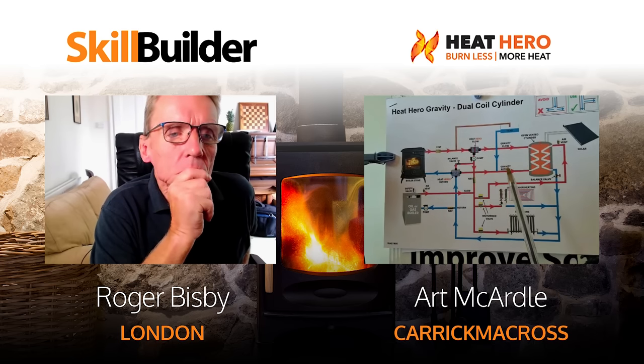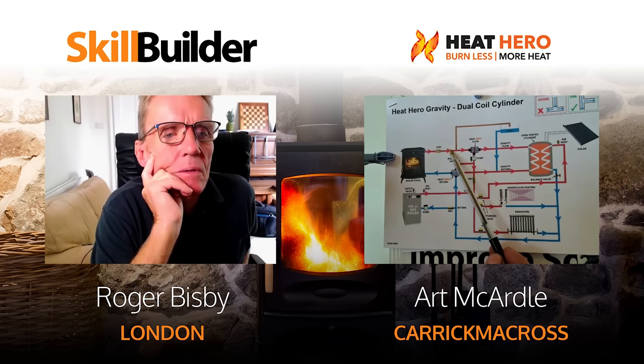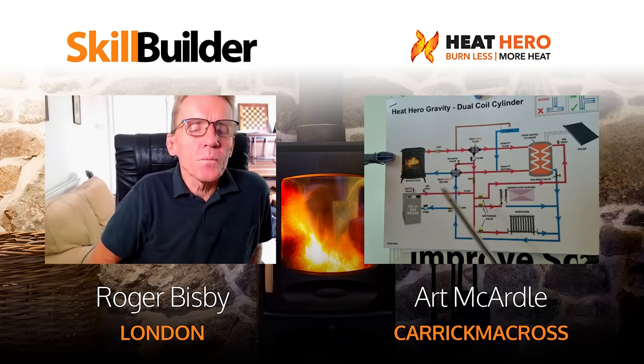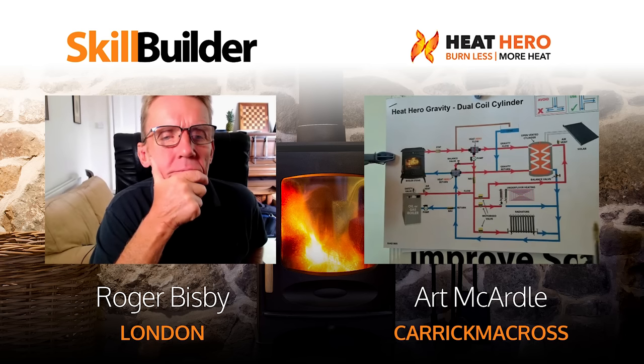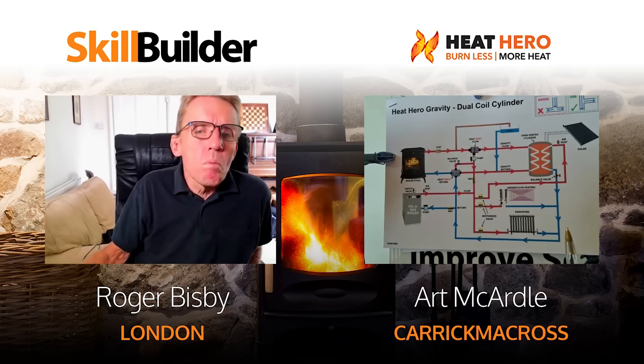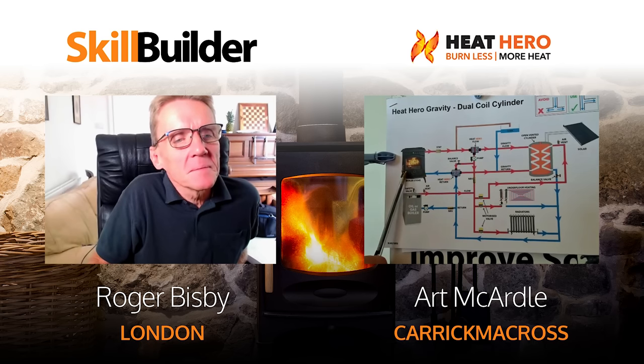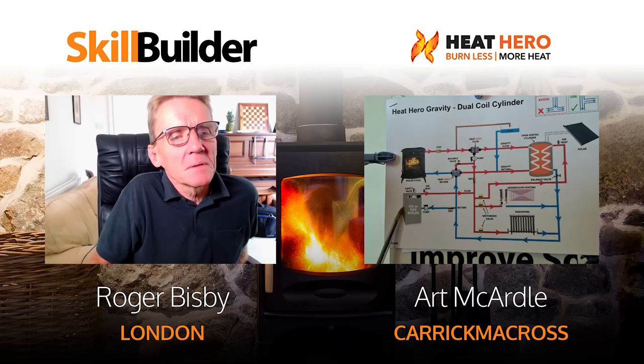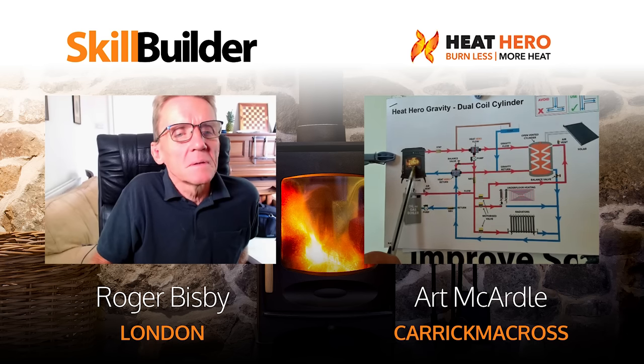We put a second stat on the stove set at about 65 degrees - 10 degrees higher than your standard stat. If it goes above 65 it automatically opens one of the zones to get rid of excess heat. We can do anything we want with solid fuel now. We have a cooker burning wood and have never bought coal - we're heating 23 radiators with it. Waterford Stanley, an Irish stove company with an R&D department, put this through their R&D and now recommend it on their website. You have twice the heat in a solid fuel stove compared to an oil or gas boiler - a gas flame is around 200-250 degrees, you could have 450 degrees in a solid fuel stove.